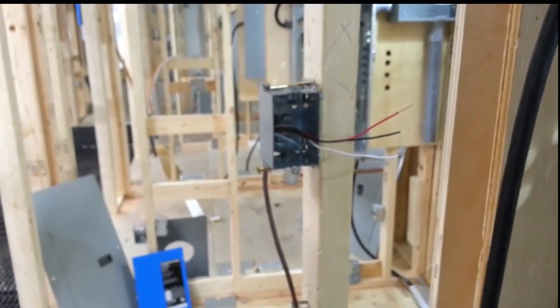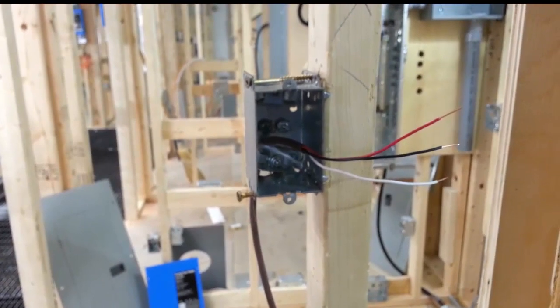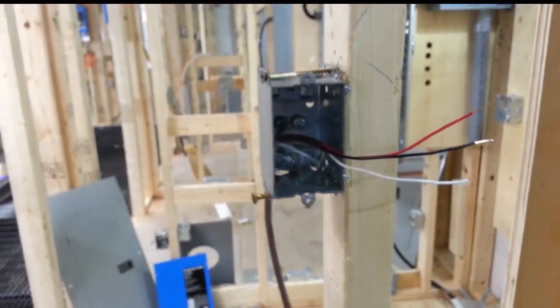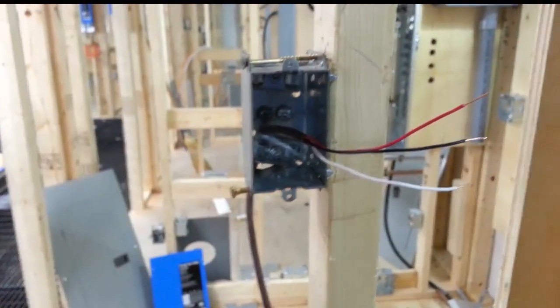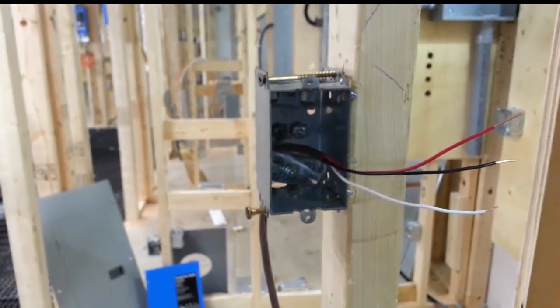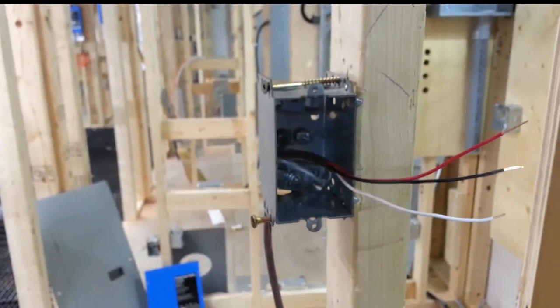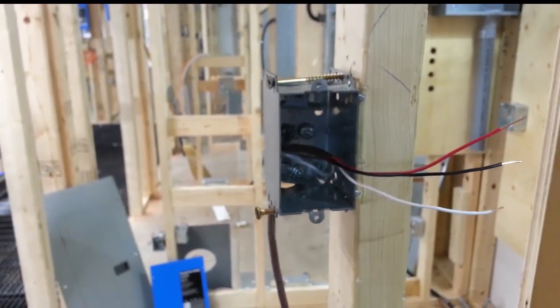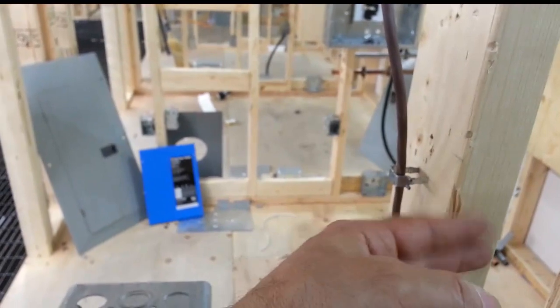Okay, let's go over where we are going to run the wires. We are going to use 18-3 gauge wire. Sorry, one of the switch boxes mounted at 52 inches. We are running the wire inside a box. Since this is low voltage wire, technically according to code, you really do not need a box. You can use a plaster ring or you can just fasten it to the drywall making a hole. So that's another advantage of low voltage wiring. The code book does not require for you to need to have a box. But we are going to use one for the lab. So we have it in the box. We have stripped some wires back and we run it down across our studs. You are still going to need your staples if it is a new installation to keep it from being damaged when coming in front and being screwed by drywall screws. So you still need your staples.